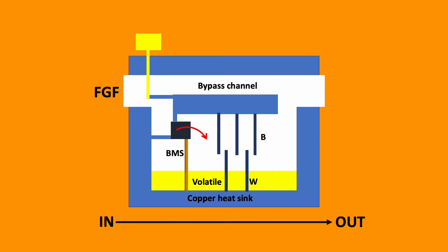In a typical plenum vaporizer, fresh gas flow moves from left to right. There are two streams: one via the bypass channel, and the other moves into the vaporizer chamber. The ratio of the amount going into the bypass chamber versus the vaporizing chamber is determined by the splitting ratio, set by the concentration dial adjusted by the anesthetist. To ensure the gas entering the vaporizer is fully saturated, we increase the surface area using wicks and baffles.